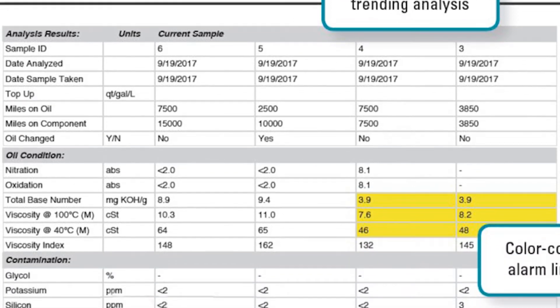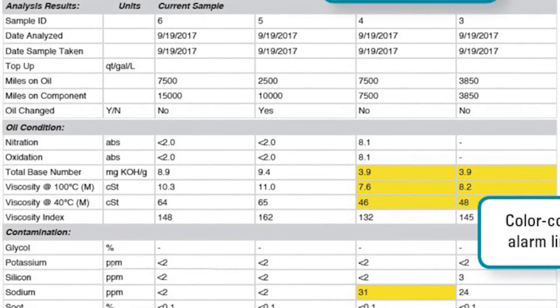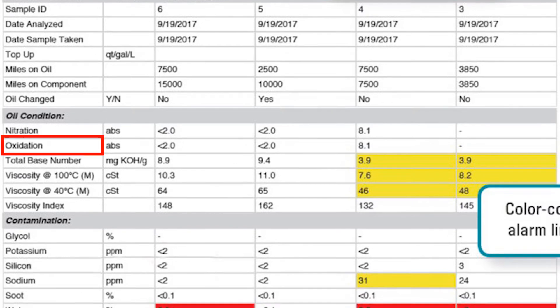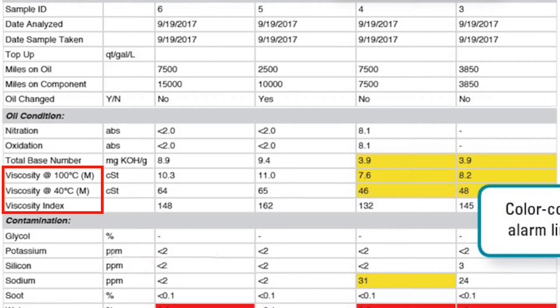Next is the oil condition parameters: oxidation, nitration, total base number, and viscosity. These indicate the health of the oil and whether an oil drain extension can be considered.